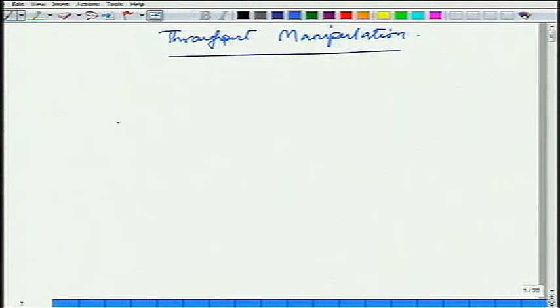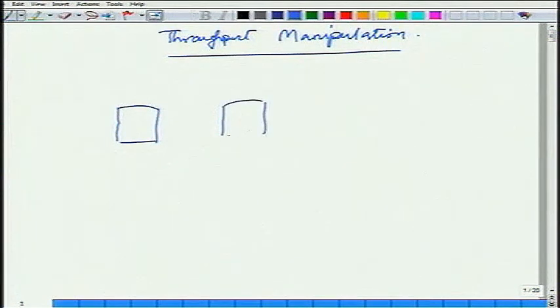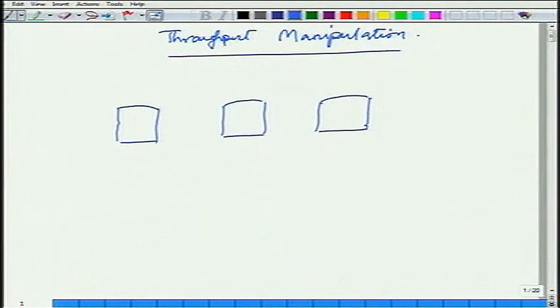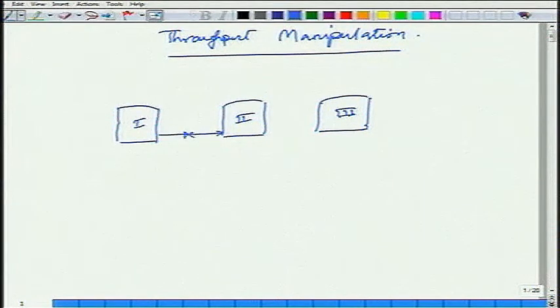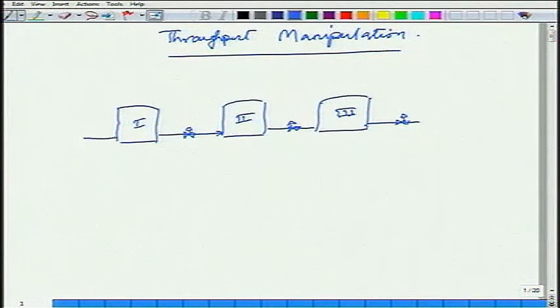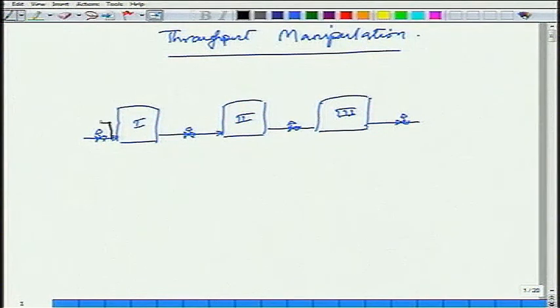Last time we quickly went through an example of tanks in series, but it need not necessarily be tanks in series. Each of these tanks could represent a process section — plant number 1, plant number 2, plant number 3 — connected in series. I can set the throughput at the feed to the unit or to this train. The feed to the train is flow controlled, then level control has to be in the direction of flow.